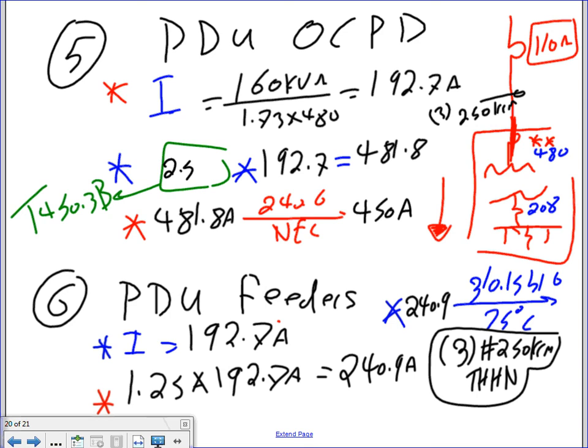Now I would like you to do one more calculation, guys. We're done basically. The other calculation is I want to see what size panel most likely they will put with this. So how am I going to do that? Let's just say I'm going to point to this and have the calculation right here. Can you do me a favor? Take the 160 kVA divided by 1.73 times 208. What do you guys come up with? Remember, there's a K. 160K divided by 1.73 times 208. 445 amps. So most likely, this panel will have a 500 amp.